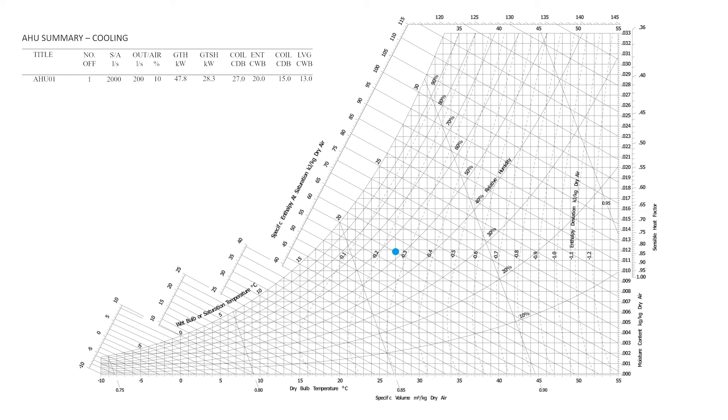This might seem fine at first, but by plotting this point on the chart we can immediately tell that the cooling process alone is not enough to achieve this supply air condition, as it is situated away from the dew point line. An additional HVAC process is needed. In this case, a small amount of reheat or a bypass air mixing system would do the trick.